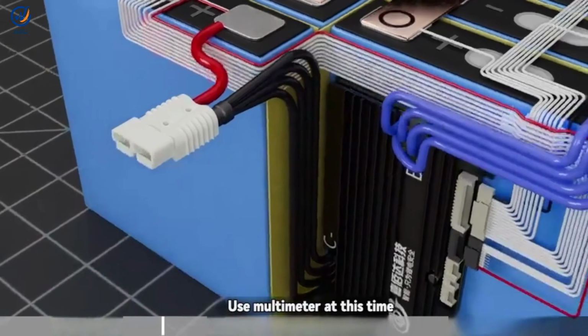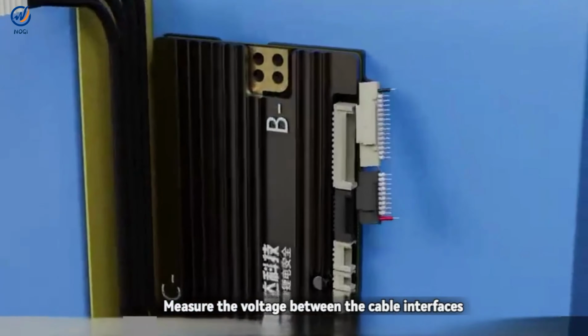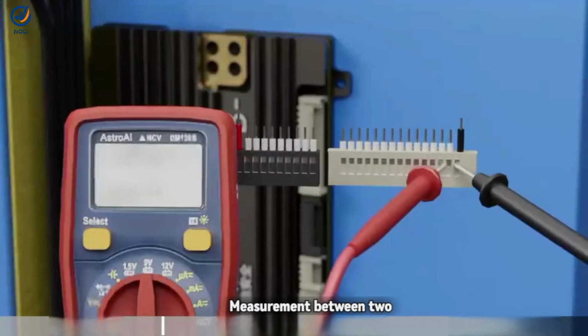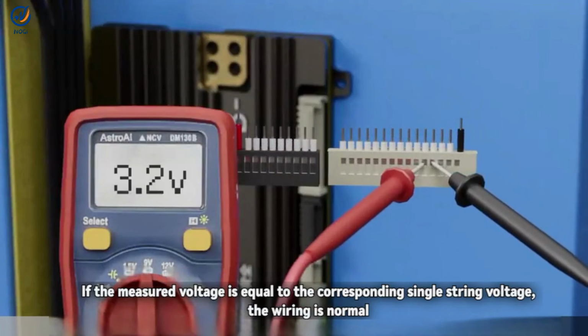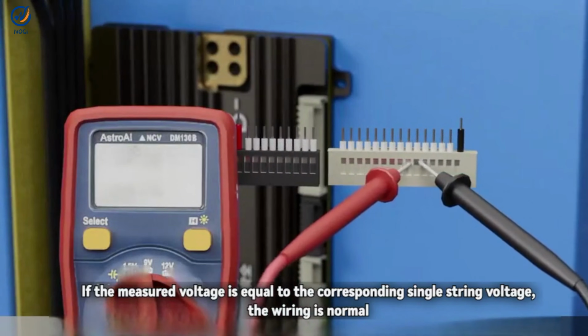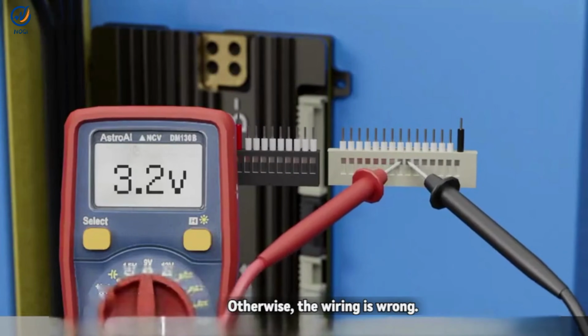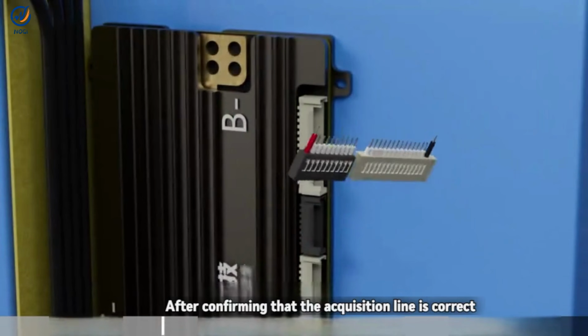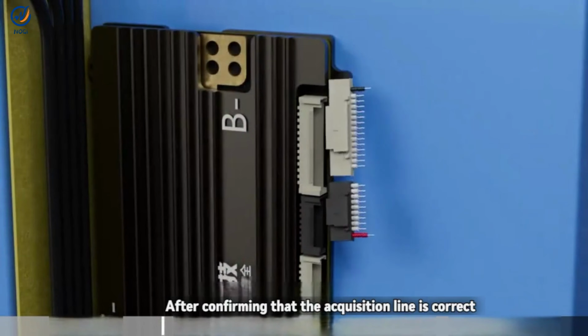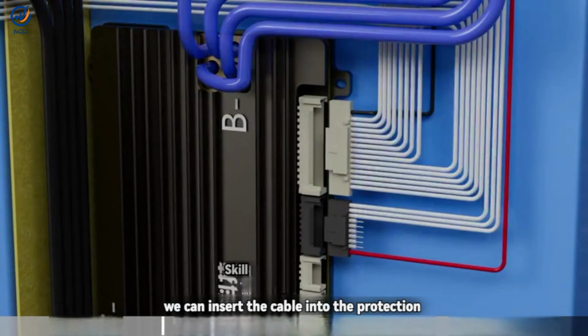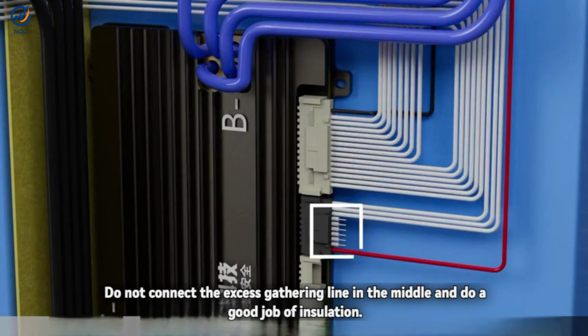Use a multimeter at this time. Measure the voltage between the cable interfaces, between each two. If the measured voltage is equal to the corresponding single-string voltage, the wiring is normal. Otherwise, the wiring is wrong. After confirming that the acquisition line is correct, we can insert the cable into the protection board. Do not connect the excess acquisition line in the middle, and do a good job of insulation.